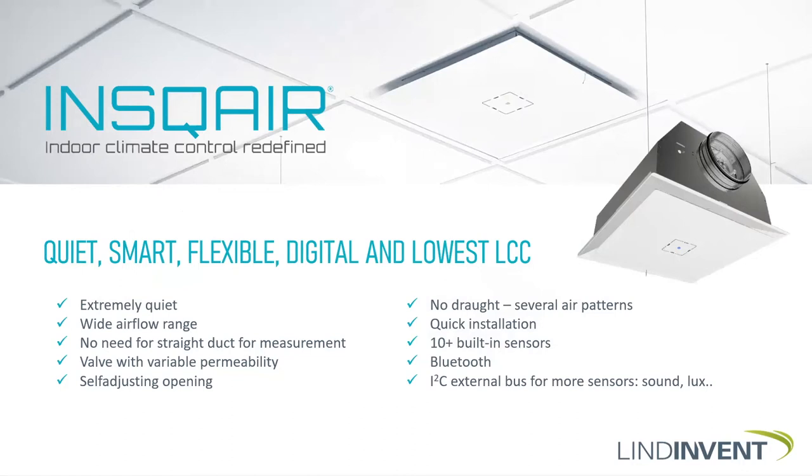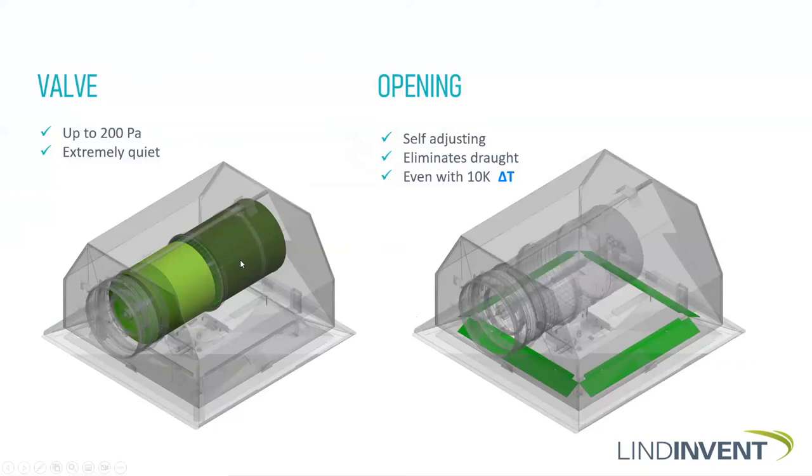And the self-adjusting opening, which I will show in the picture, is the thing that makes it possible to work with really cold air, which means less heating and then actually less cooling. And the installation, the sensors, the Bluetooth connection, it is to make it the best of the best. So with this valve that you have here to the left, we can actually have a pressure drop up to 200 pascals without causing any noise.